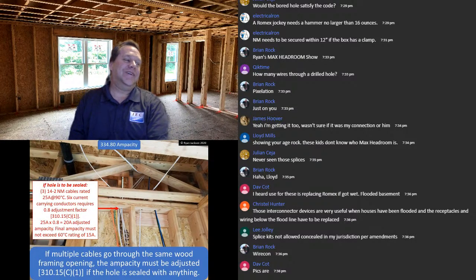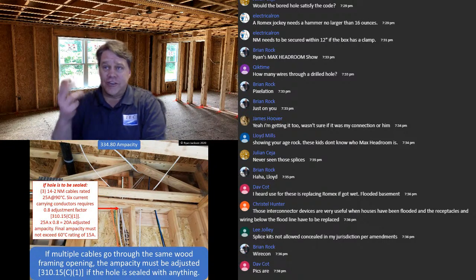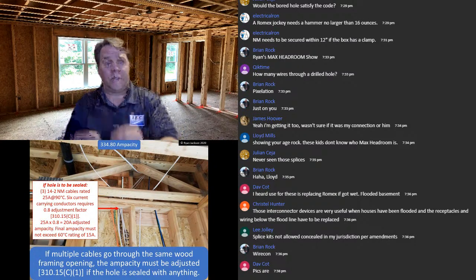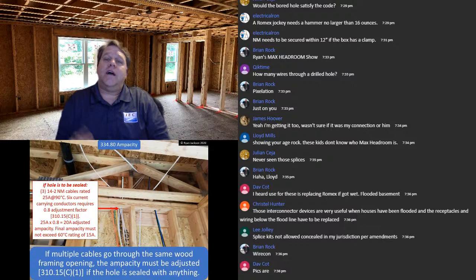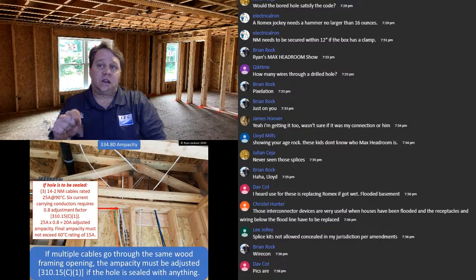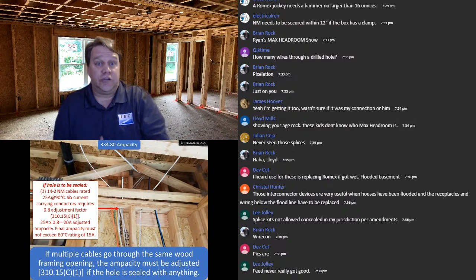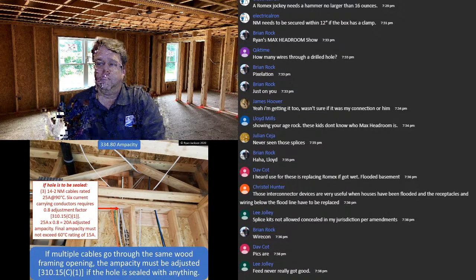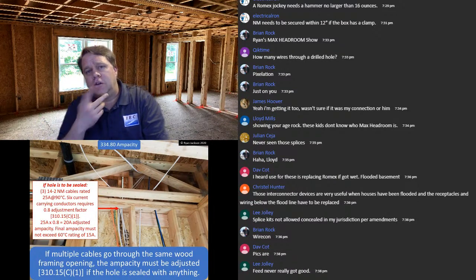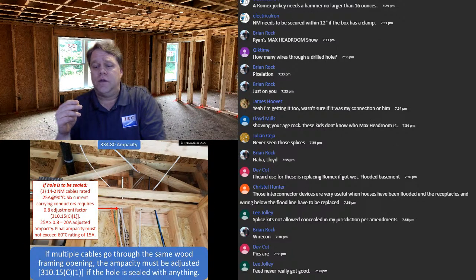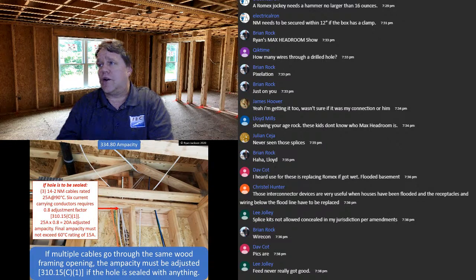Yeah, from the 80s. I'll tell you where else you can use that little splicing device. What if you have an old house that has 60 degree rated NM cable, where the actual cable is 60 degrees or 75 degrees? If you buy a new luminaire, one of the things you'll notice is it says you have to have 90 degree conductors. So how do you deal with that if you have to change your light and your house doesn't have 90 degree conductors? Well, splice on one of those things to your new 90 degree conductors.